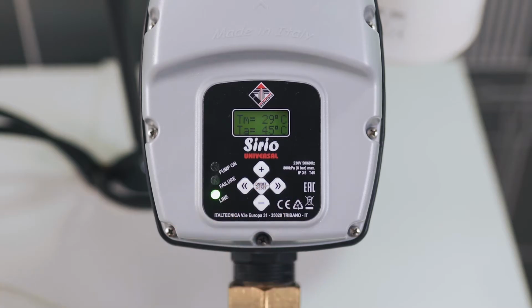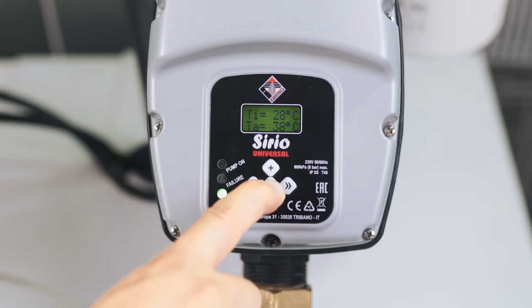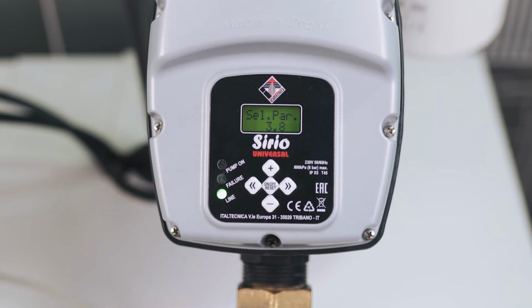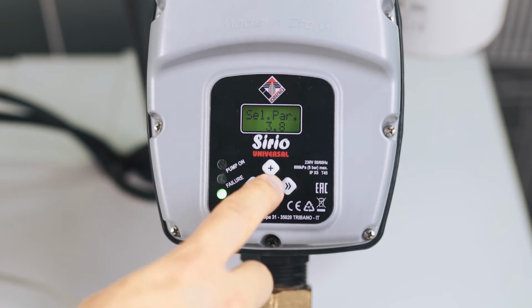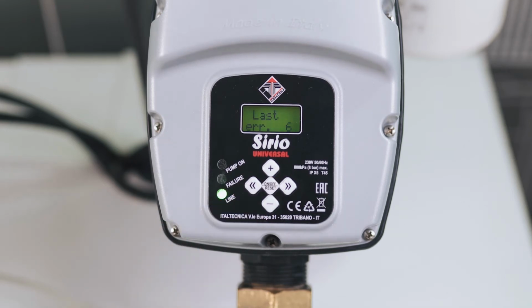specific error. To log into the advanced menu, Sirio must be set in standby, and we go to the temperature screen, pushing on the arrow. We press the central button until this bar appears on the display. Now it's enough to set the desired advanced parameter, for example 3.8, and we can see the last error.